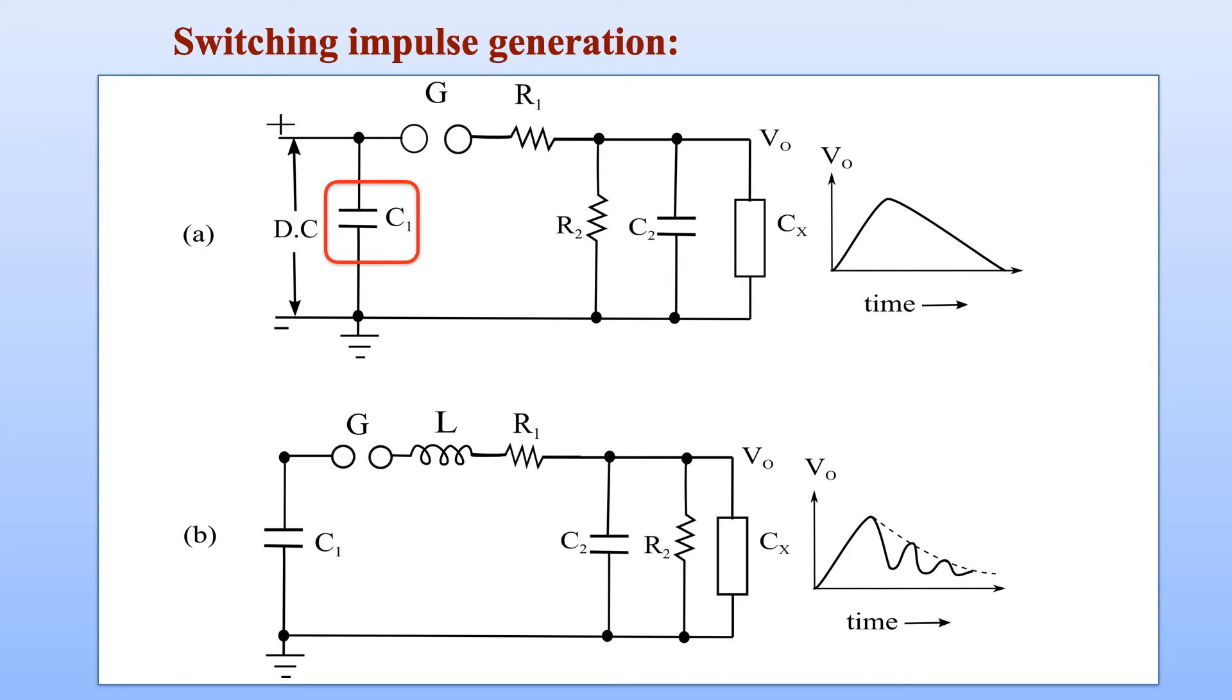Let us now check the switching impulse generation circuit. This is a basic switching impulse generation circuit derived from a lightning impulse generator. The principle of operation can be understood with two configurations: one without a series inductor and other with a series inductor. The above circuit shows an input capacitor or generator capacitor C1 which will be charged from a DC source or high voltage DC rectifier.